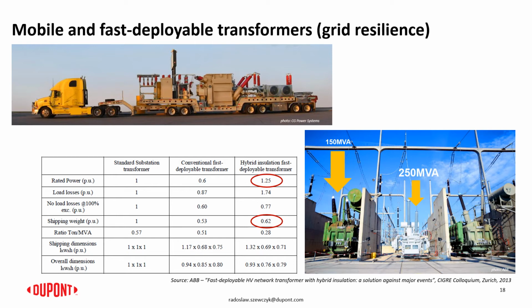Then, when moving to the larger transformers, what is shown on the top of the slide is the typical mobile transformer for the emergency installations, the transformer which is fully assembled and filled with oil and ready to travel as such, together with the components of the substation and with its cooling system on the back of the trailer. So this is the solution which is quite common in North America today for the power utilities, while the newer developments include the growing size of such transformers.